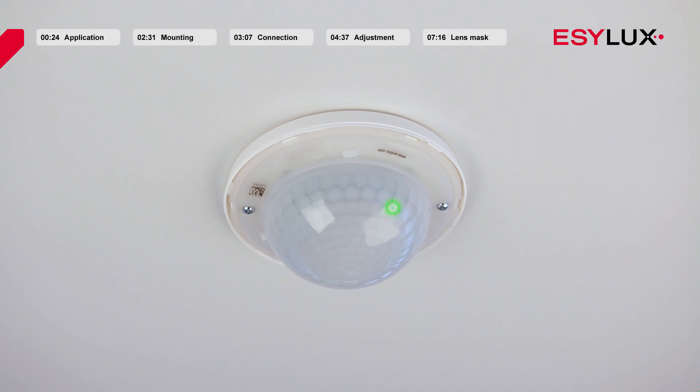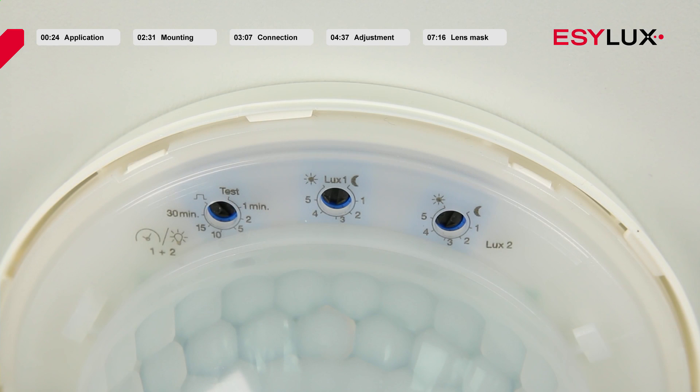When the warm-up phase is complete, the red LED flashes as soon as a movement is detected in the field of detection. If the presence-dependent switch contact is active, the green LED flashes simultaneously. If the detector has been switched to programming mode via remote control, this is indicated by a blue LED. The ceiling mounted presence detectors are delivered with a pre-configured program and are set to fully automatic mode ex-works.